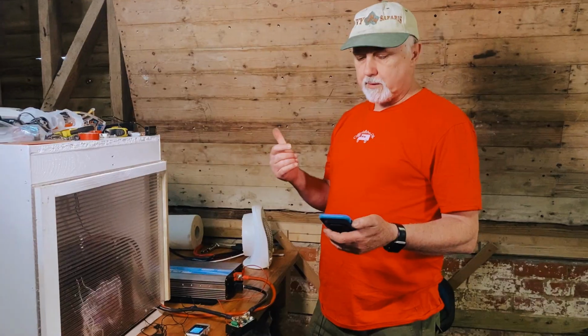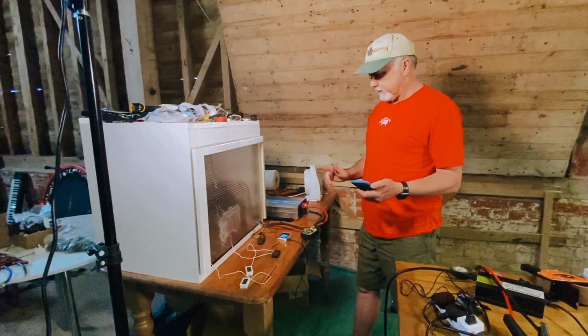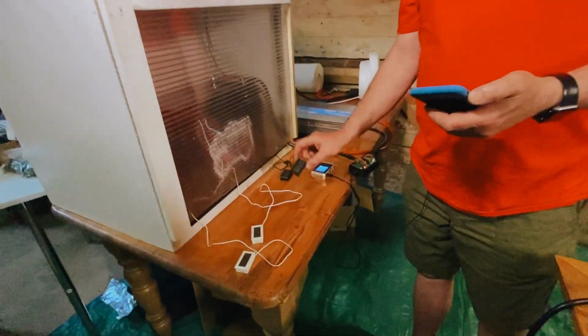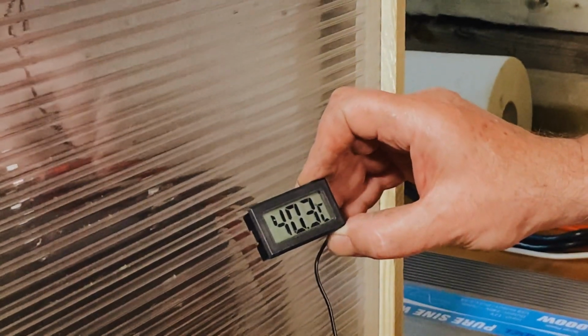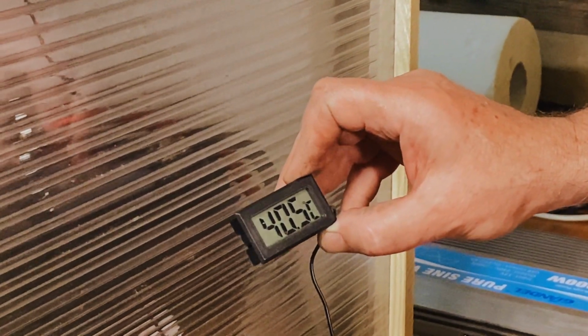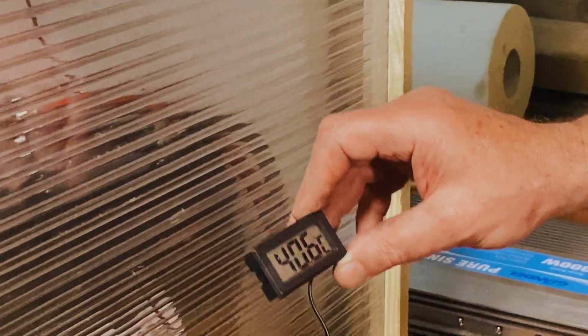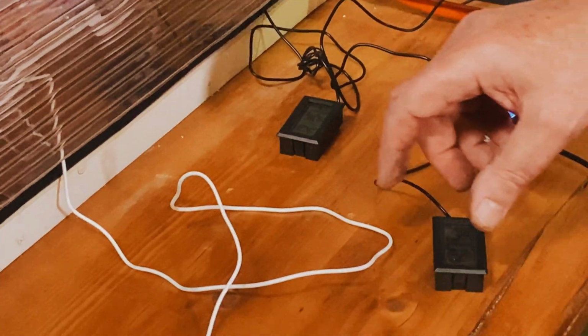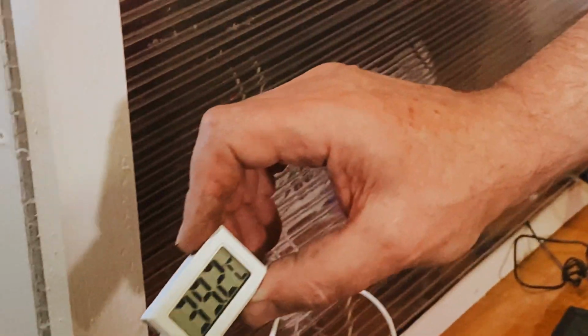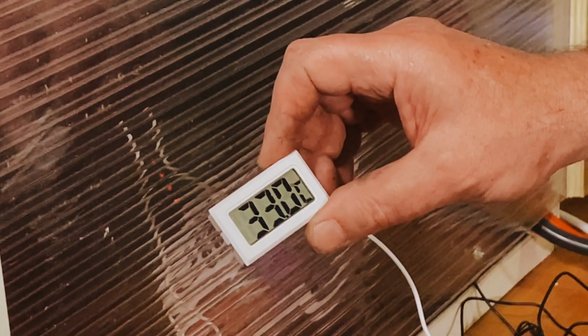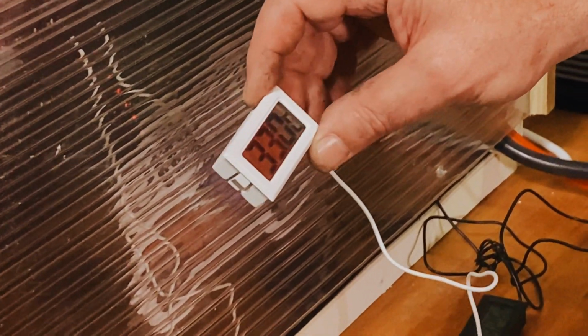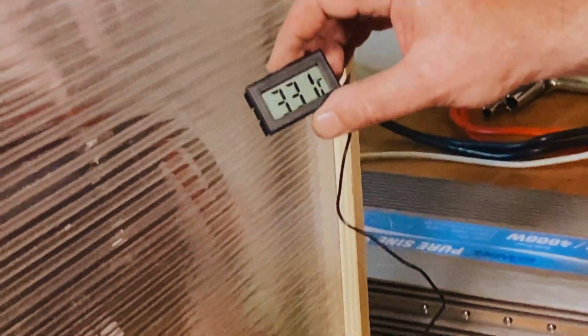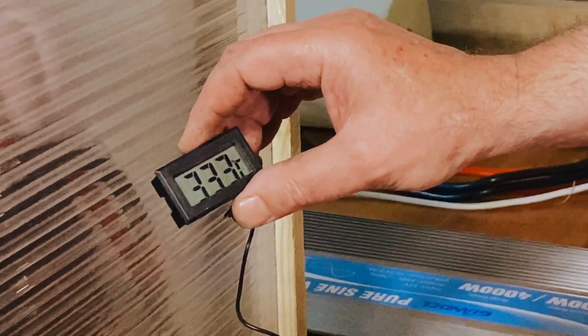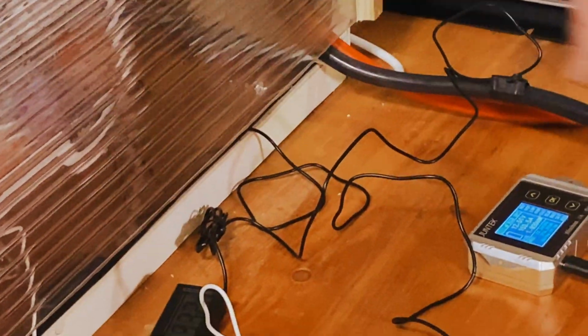So stay tuned. We've been running this for 10 minutes now. The hottest terminal is the negative terminal - interestingly it has come up to 40 degrees, gaining about 11 degrees, followed closely by the main positive which has gained close on 10 degrees as well. The positive cable is at 33, so it's only gained 3-4 degrees. The external negative cable has gained just a few degrees too, very similar to the internal cable.